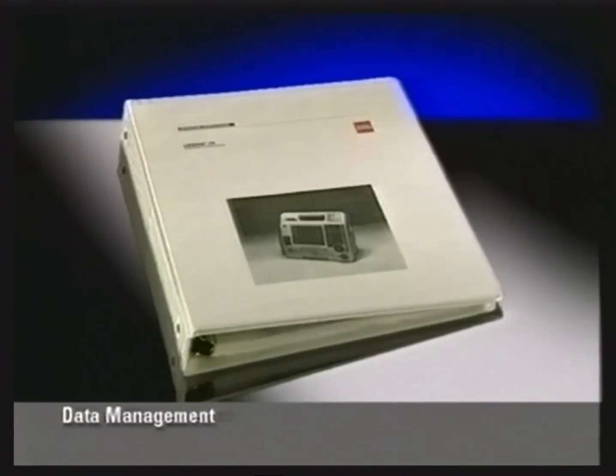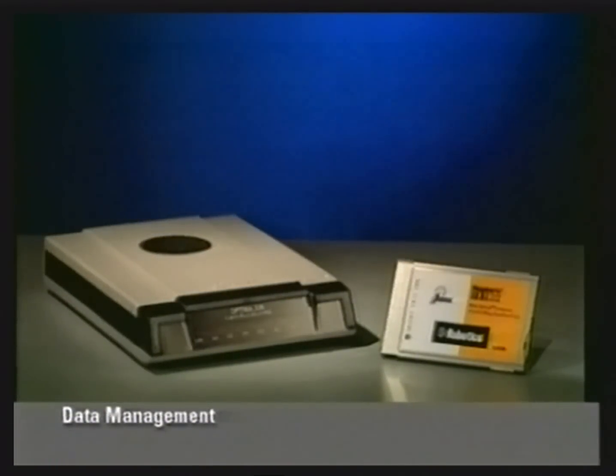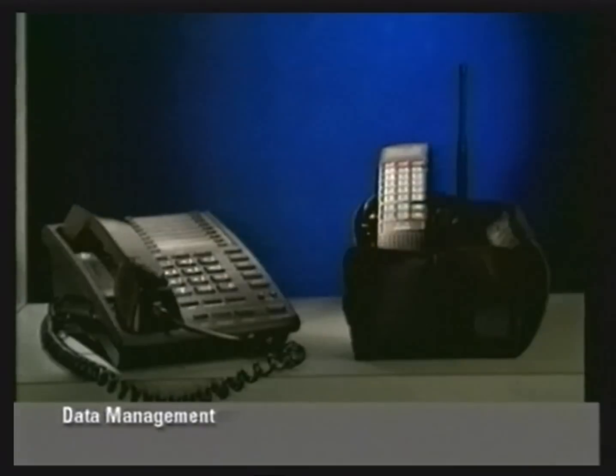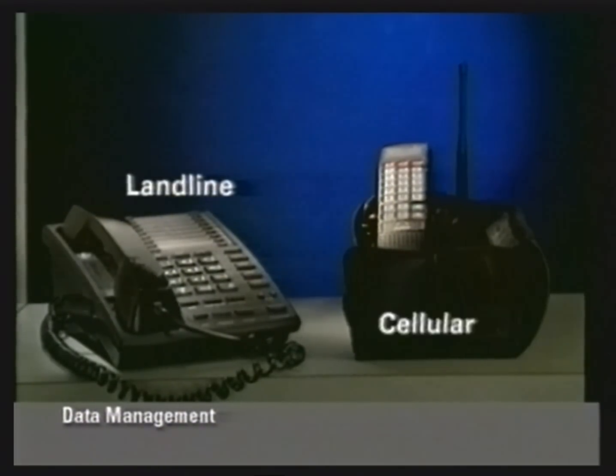Before patient data can be transmitted, the receiving sites must be entered on your Lifepak 12 defibrillator monitor. Refer to your operating instructions, Section 9, Setting Up Transmit Sites, for further details. The Lifepak 12 defibrillator monitor must have either an internal PC card modem or an external modem in order to transmit patient data. For help in selecting which modem is correct for your application, contact your local Physio-Control sales representative. These modems may be connected to either a standard landline telephone or a cellular phone.